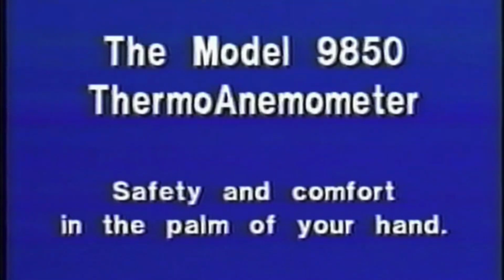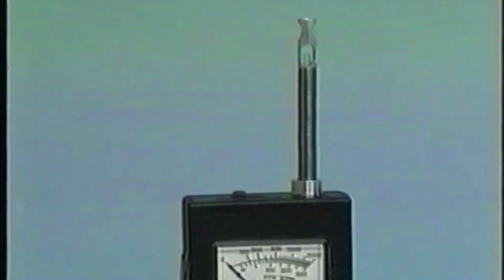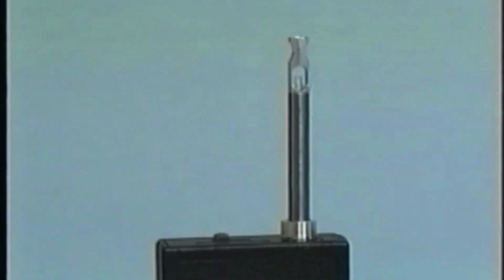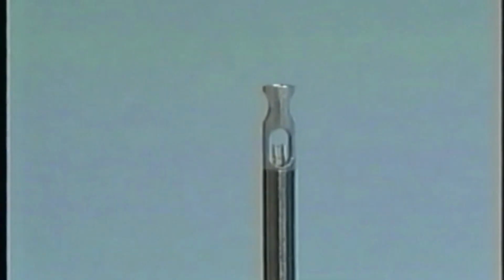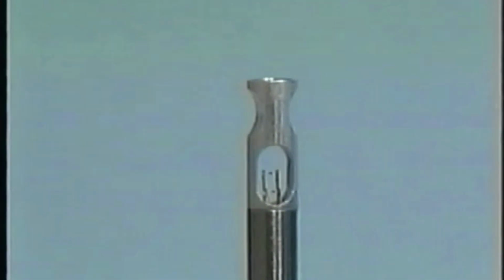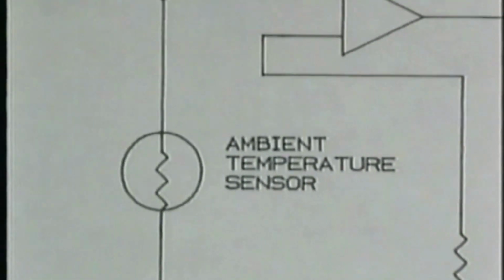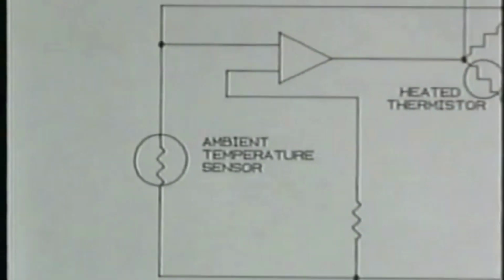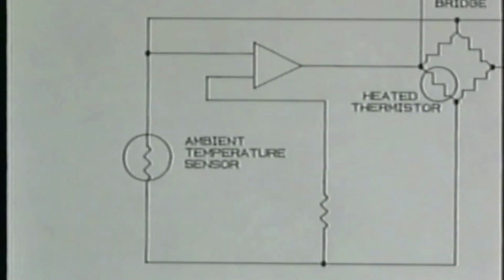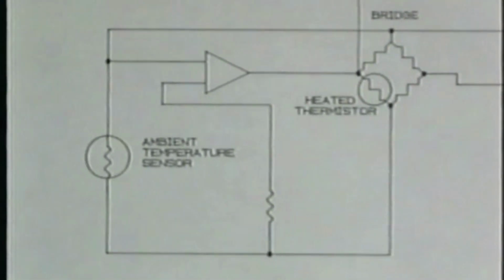How does the ThermoAnemometer 9850 work? Two thermistors are used, positioned at the end of the probe and exposed to the airstream to be measured. One senses the ambient temperature of the airstream. The other is then heated by the circuit above ambient. As air passes over this heated thermistor, it produces a cooling effect proportional to the airflow velocity, and a change in voltage across the thermistor is created.